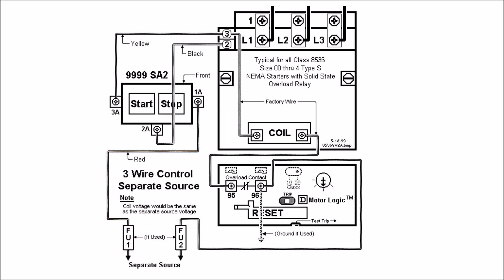2A on your start stop push-button assembly will actually go to terminal 2 on that auxiliary contact up there for your holding circuit and 3A will go to the terminal 3.